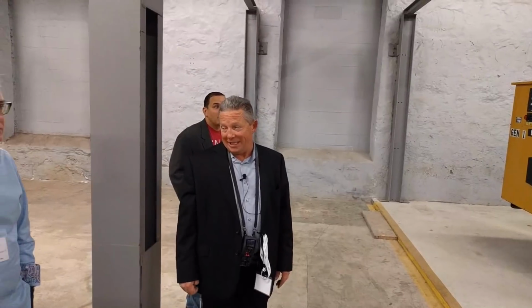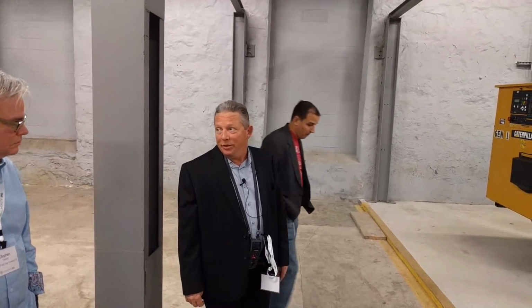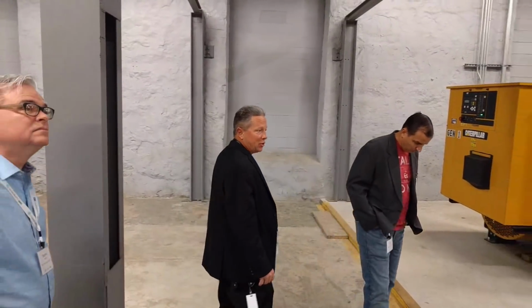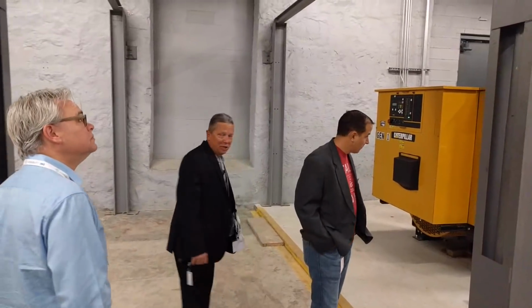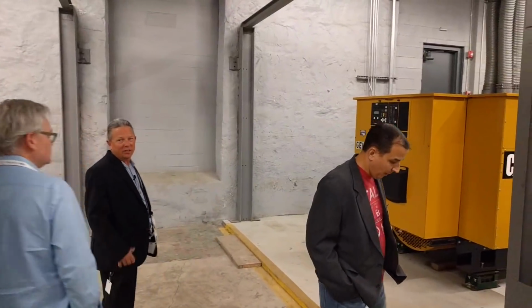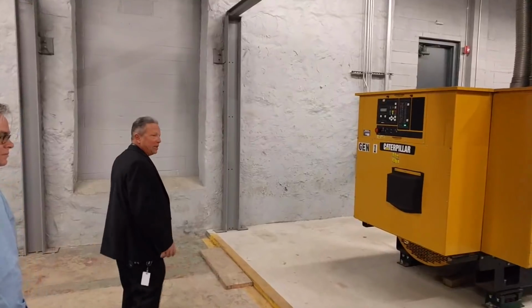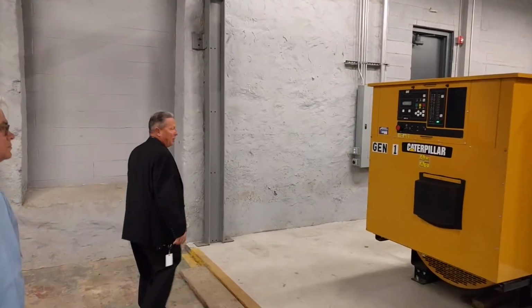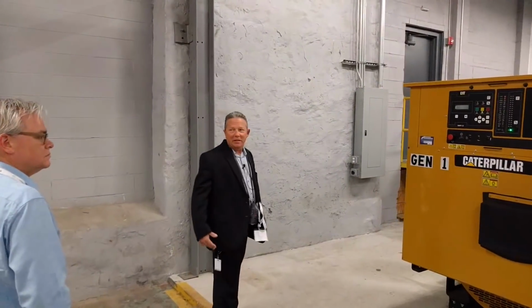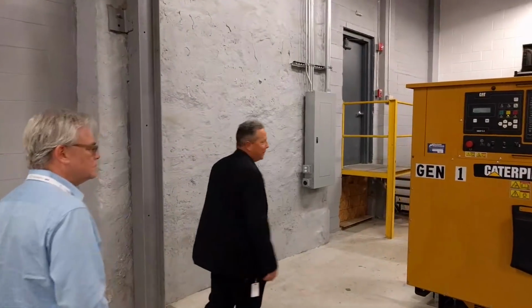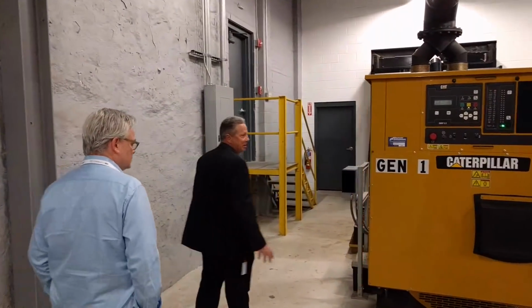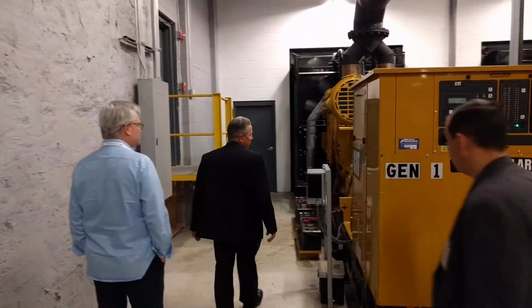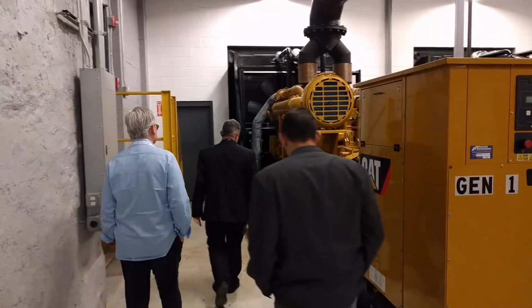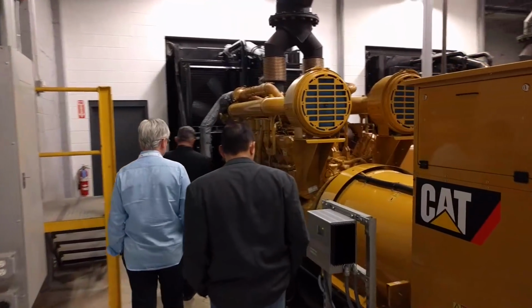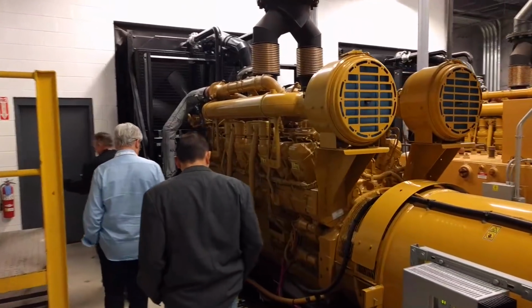Per the limit, we're at 65 dB at the curb. So Massachusetts only allows you to run 180 hours a year on generator, unless it's declared a state of emergency. You can pay some fees for the extra pollution and go further. But in general, the best practice is keep your use to 180 hours or less. So that's 360 hours between 2 gens. So we're in pretty good shape.